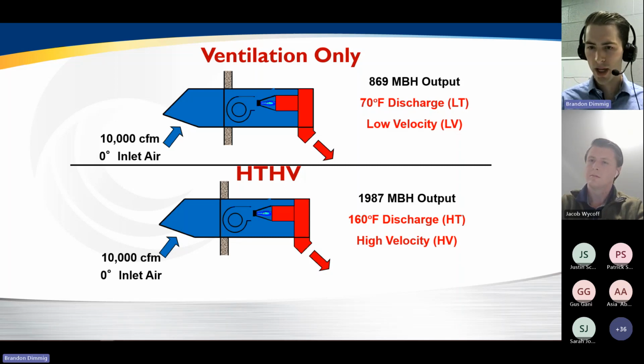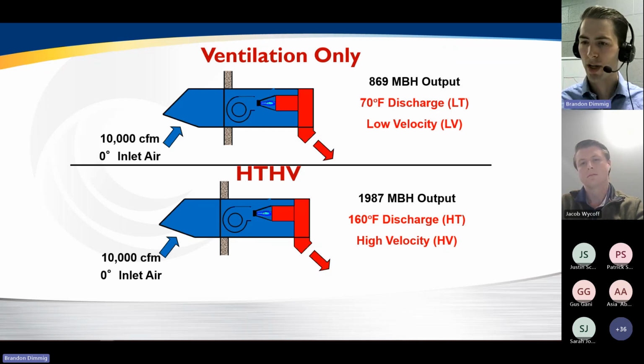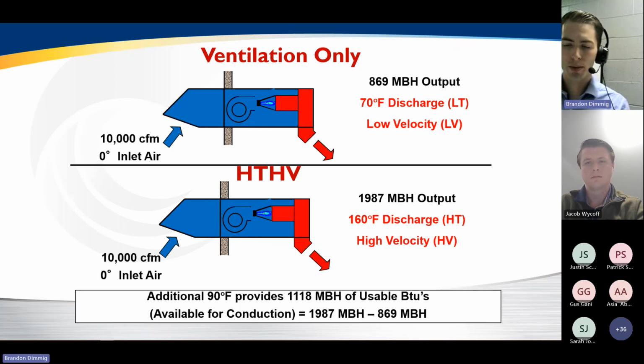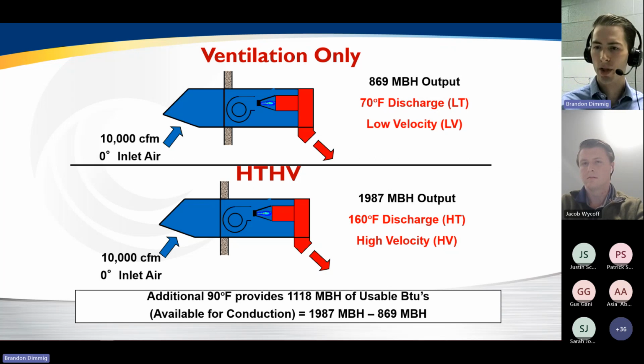Take that same unit and change nothing but increase the discharge temperature by 90 degrees to a total discharge temperature of 160 degrees. And now you've got a total MBH output of just under 2,000. So the important part of this is the difference between those two numbers. We call that usable or net BTUs. And that number, in this case, is a little over 1,000 MBH. All that heat is available to meet the conduction load of the building.